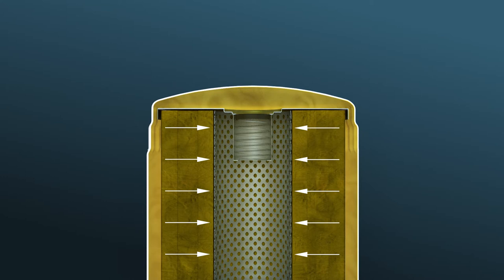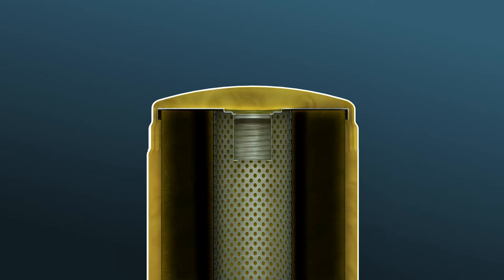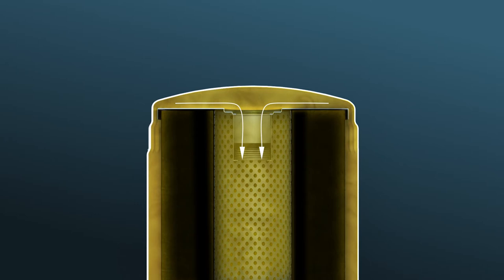The bypass valve is an important safety feature to prevent element failure. By opening at the right time, it safeguards the oil flow to the compressor element, even if the oil filter is clogged or at start-up when oil viscosity is high.